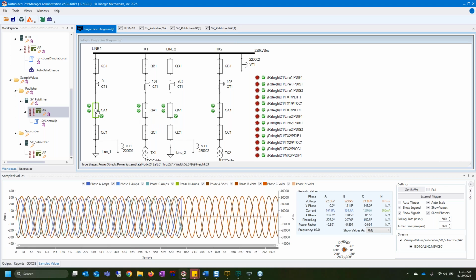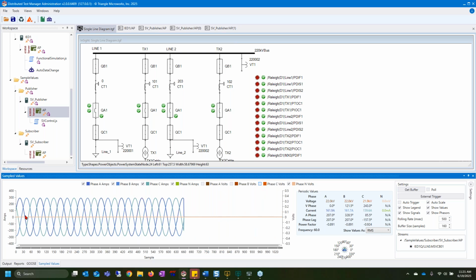Now, if I open this breaker, I have it set to stop on event change on this breaker. And you can see that several of the amplitudes, so if I hide the voltages here, you can see the current was coming down this line. The subscriber here was able to recreate the curve based off of the samples it was receiving. And then once the breaker opened and obviously the CT dropped to 0, we then lost that curve there and we're able to replicate the dead-ending of that current. So yeah, sampled values can be used to monitor the different phases of your amplitudes and voltages coming across the line. And this is just a very quick example of how you can see that in our simulator tool, DTM. And with that, I will pass it back over to Jackson, I think, for controls and then for the wrap up.